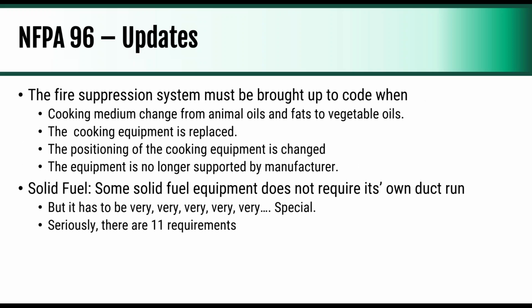The last two, and these are, again, not huge issues. The fire suppression system must be brought up to code when really any change is made to the system. They specified and called out that cooking medium change. So if you have a fryer that you were cooking with vegetable oil and you switch to using animal fat, you are supposed to redo the fire suppression. Most people should be doing that anyways, but now it's part of NFPA 96. If cooking equipment is replaced, even if it's like for like, the fire suppression should be brought up to code.